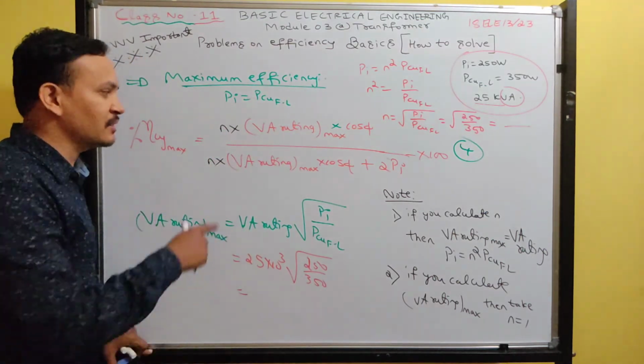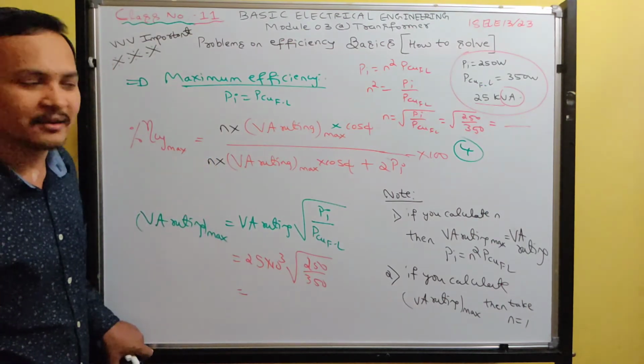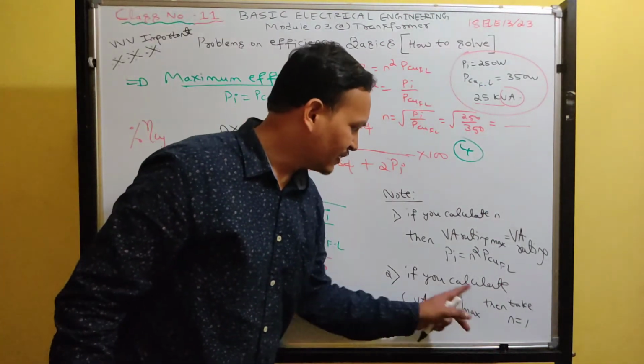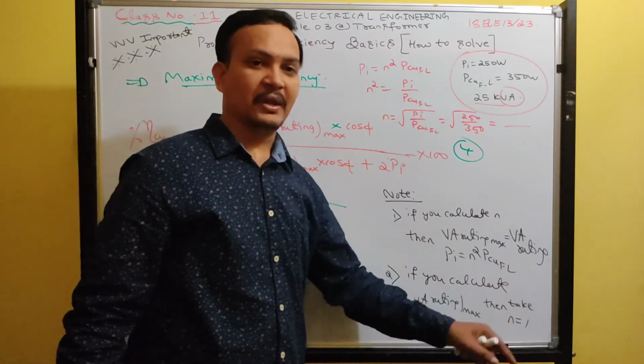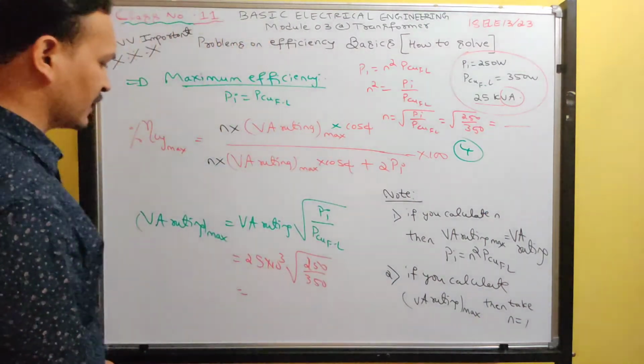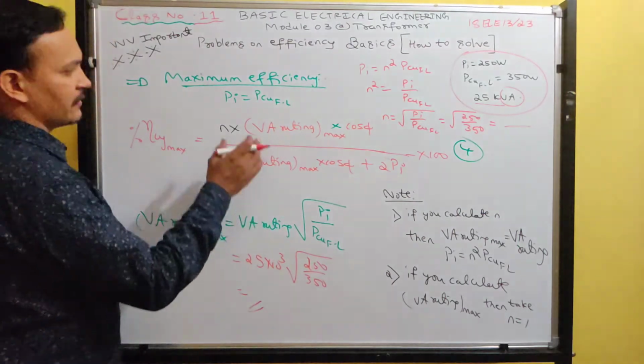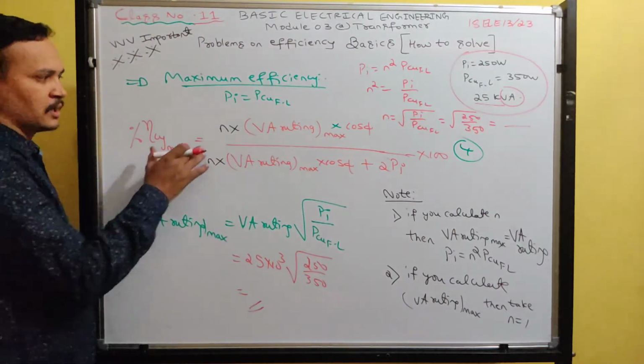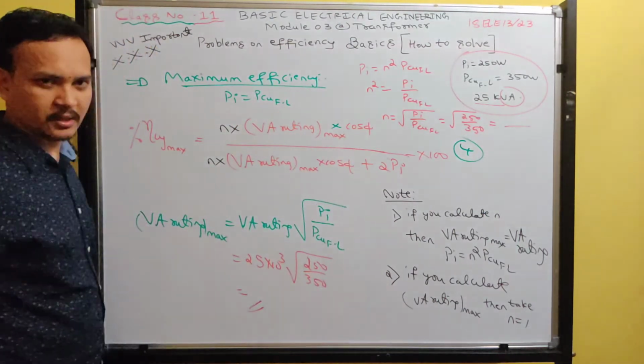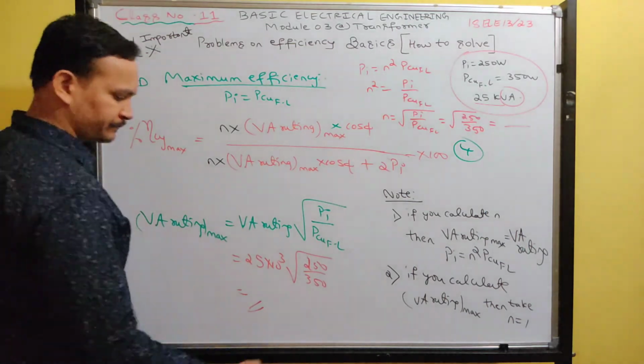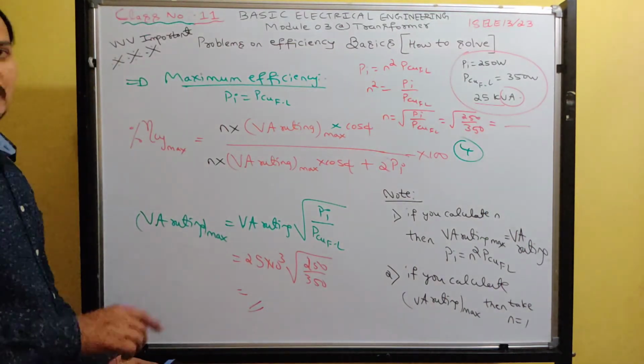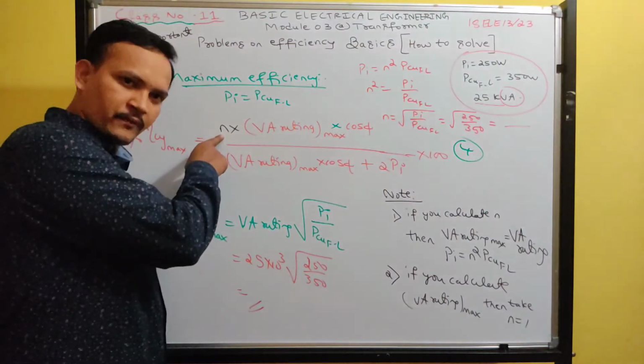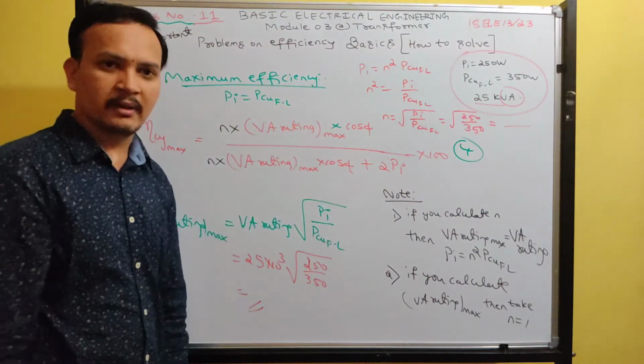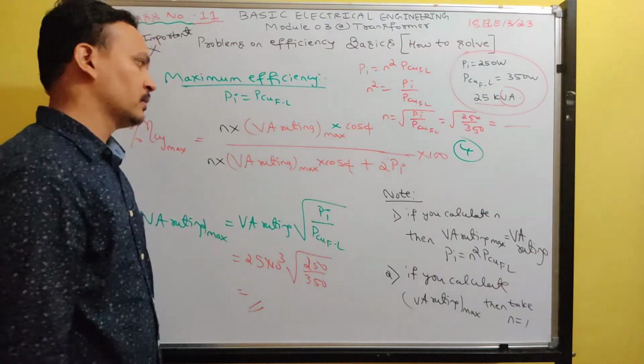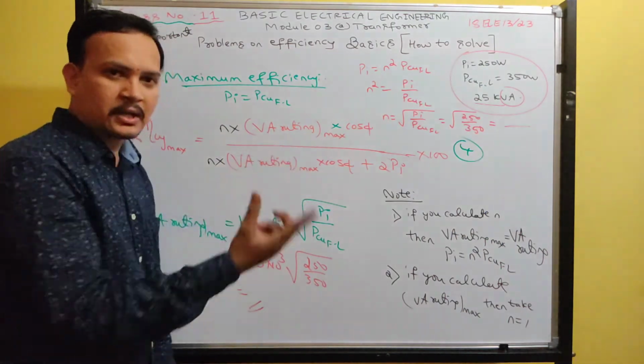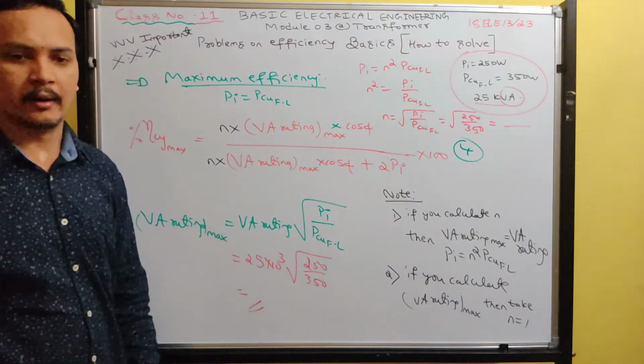Under that condition, don't calculate n. You take n is equal to 1. If you calculate kVA rating max, take n equals to 1. So, got it, guys? So this is the efficiency. You can determine maximum efficiency at any loading condition, any power factor. Understood? If you find load at maximum efficiency, then you take directly kVA rating, the volt ampere rating. If you calculate VA rating max, then take n is equal to 1.